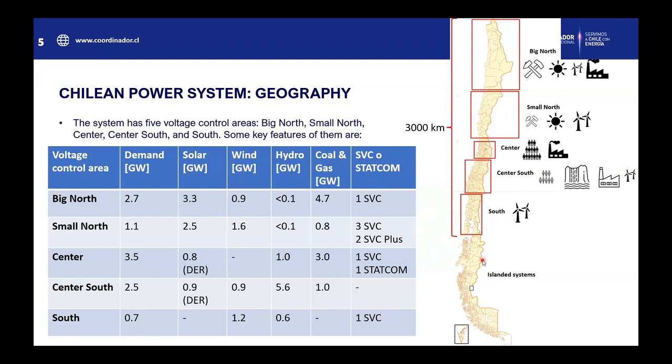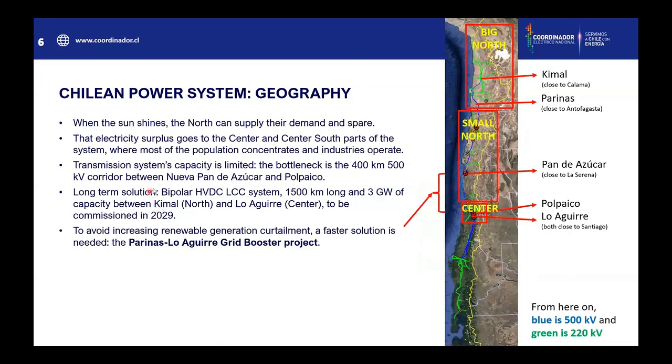With all of this in mind, you can see that the north — the big north and the small north — have a lot of solar and wind capacity installed, even greater than their demand. So when the sun shines, the north can supply its own demand and can spare. The electricity surplus goes to the center and center-south parts of the system, where most of the population concentrates and industries operate. But the transmission system capacity is limited. The bottleneck is the 400 km, 500 kV corridor between Nueva Pan de Azúcar and Polpaico, linking all the north and the center part of the system.